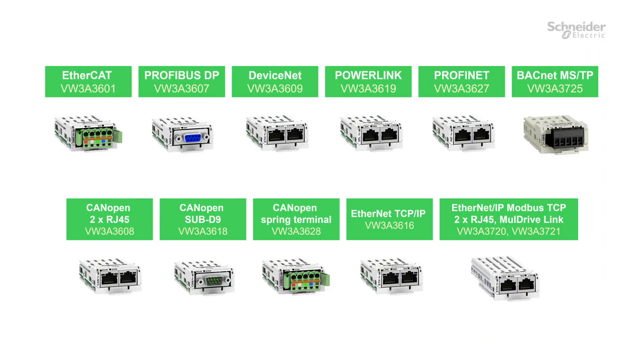Depending on the fieldbus module used — embedded or option — these errors could be triggered by the product: ETHF, CNF, COF, SLF1, or INFM. These errors are the result of a communication interruption. We will help you understand and solve these communication errors.